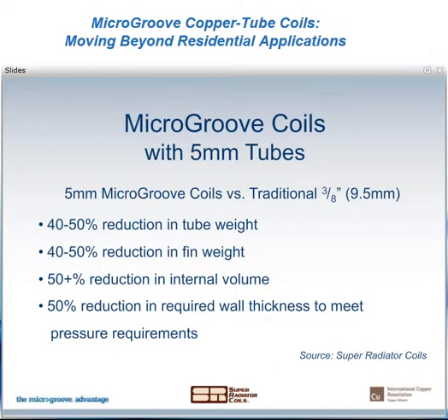At this point, we're going to start comparing coils that are made with conventional 3/8 inch or 9.5 millimeter copper tubes, and we're going to compare those coils to those made with smaller 5 millimeter tubes. And because this trend is so prevalent, we're going to continue this comparison throughout the rest of this webinar. Now, the word microgroove isn't associated with any one particular tube size. It just simply refers to the trend to downsize tubes, and we're not really sure right now where that trend is going to end up.